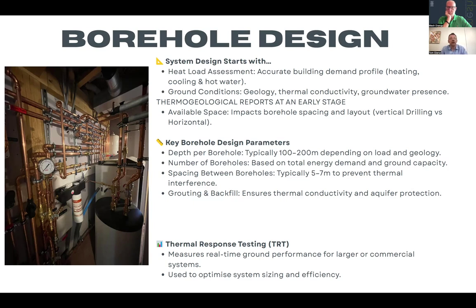But if you are going into the chalk, which is well saturated, we'll probably fill the borehole with some sort of shingle, which allows the water to flow through the shingle, and water provides great energy input, and that provides good transfer. That improves the efficiency of that section of the probe. So that's the main thing. The top part of the borehole is normally filled with some sort of grout bentonite to seal the borehole, so any of the surface water cannot penetrate into the boreholes and provide any debris or damage the aquifer.